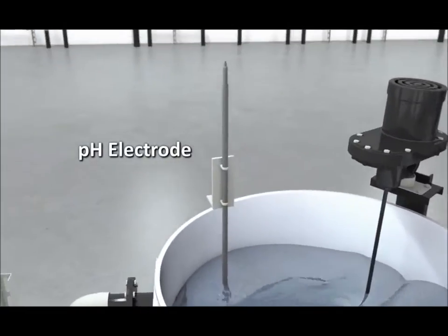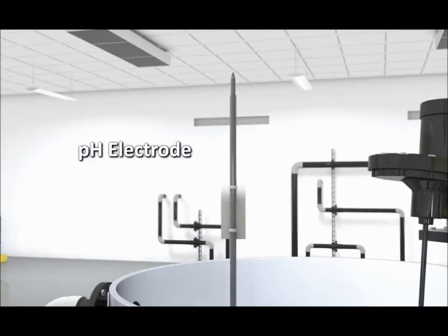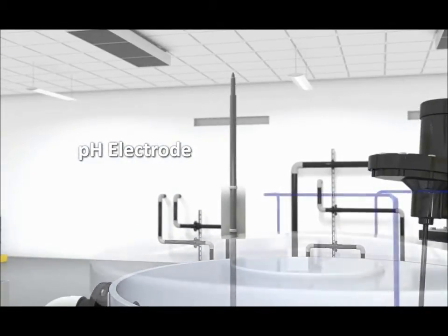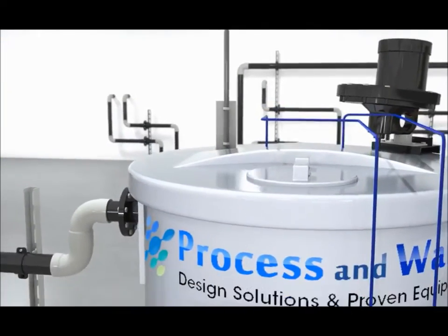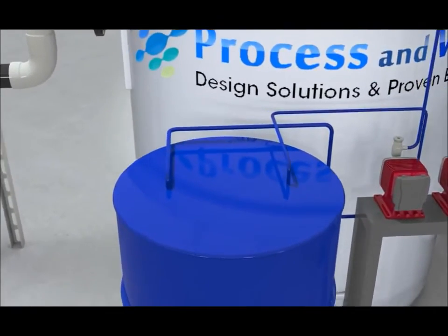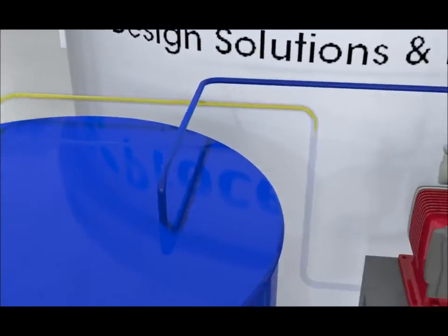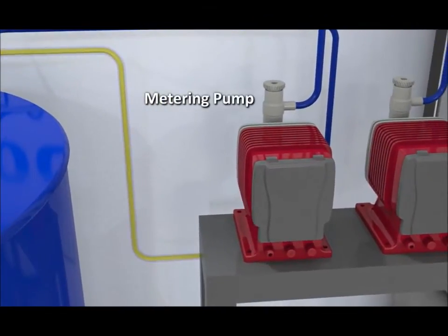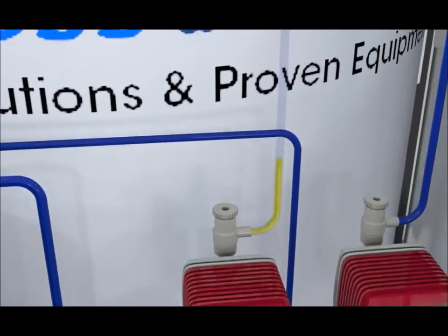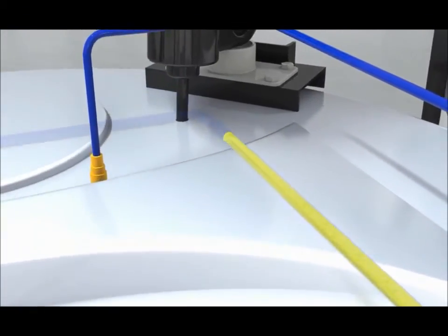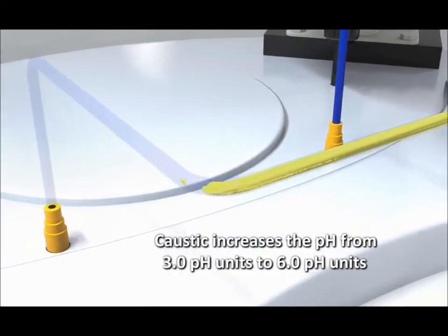The pH electrode senses the pH and displays the results on the control panel. The chemical metering pump dispenses caustic from the first chemical drum, through the metering pump, to the tank to increase the solution's pH from 3.0 pH units to 6.0 pH units.